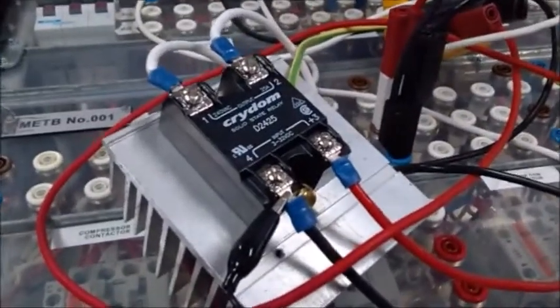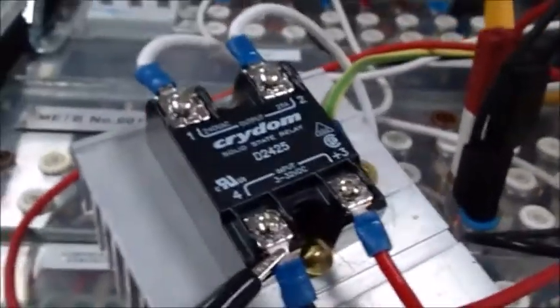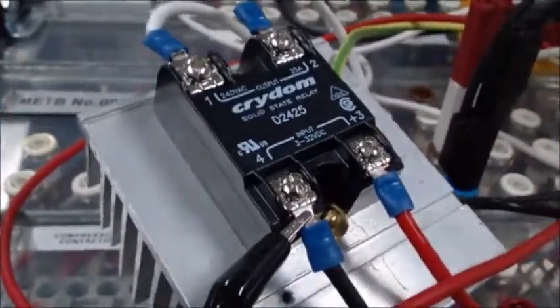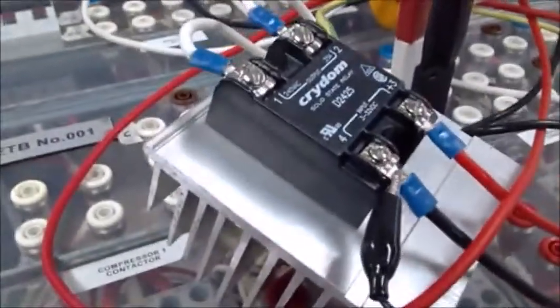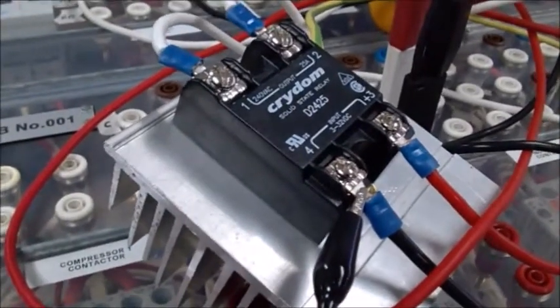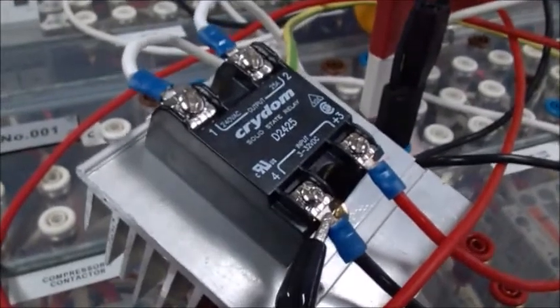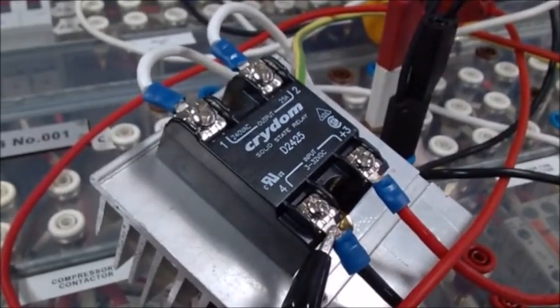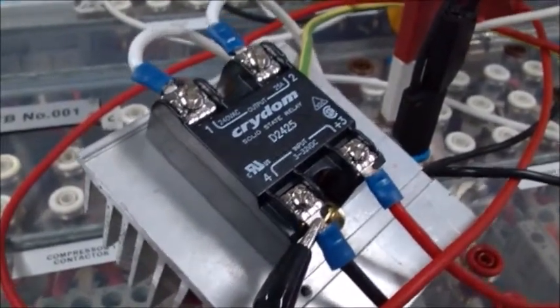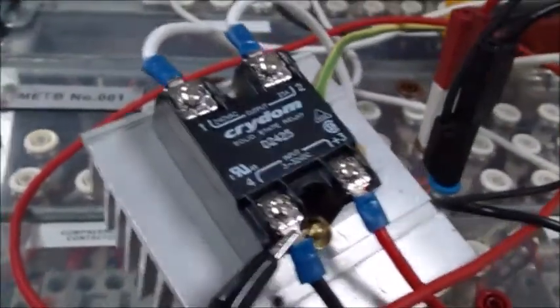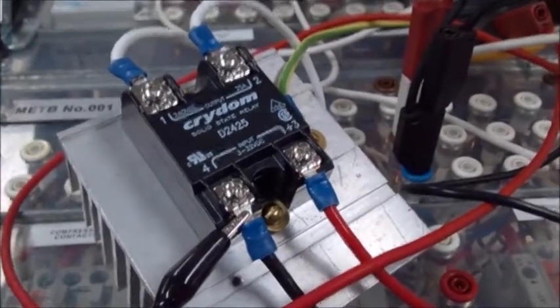Not a lot goes wrong with these. They're pretty decent. The only thing they don't like are short circuits. All semiconductor transistors hate short circuits, earth leaks, anything that causes a massive short will take them out very quickly. You're still going to make sure that you don't just apply them to a heat sink. You should put silicon grease or a heat transfer paste on them to protect them. But a very flexible device. Of course, you are limited as to what you want to control with them. You certainly wouldn't want to pulse outputs like that to a device that was inductive. It wouldn't like it very much. But if we're looking at a purely resistive circuit such as a heater, it's a perfect example of a good use for this particular design.